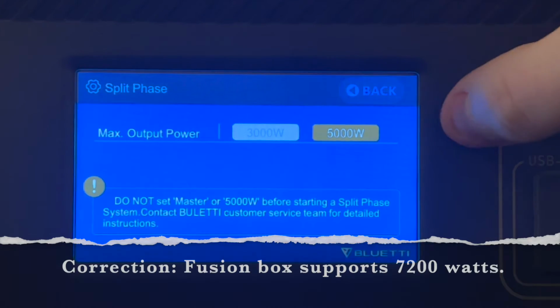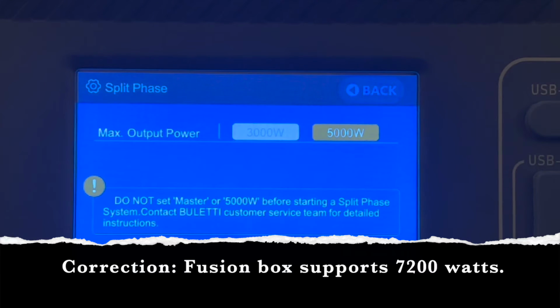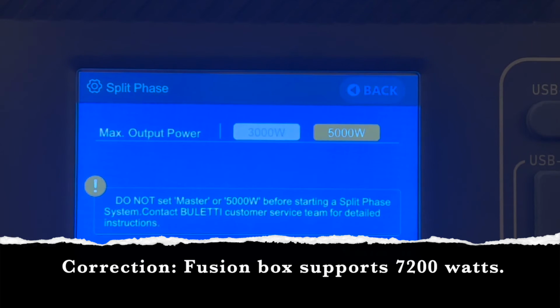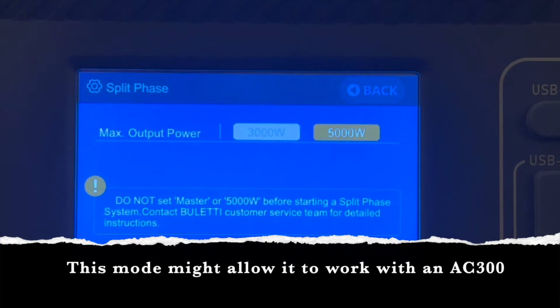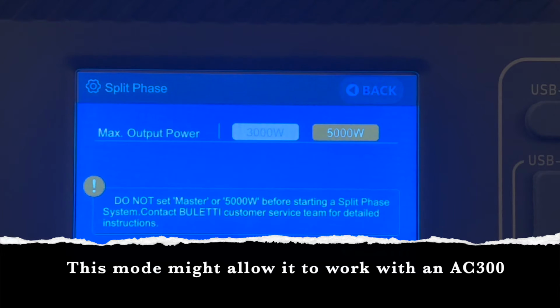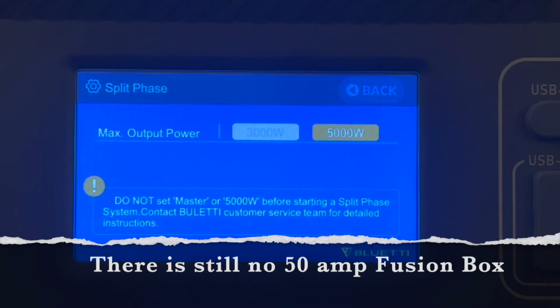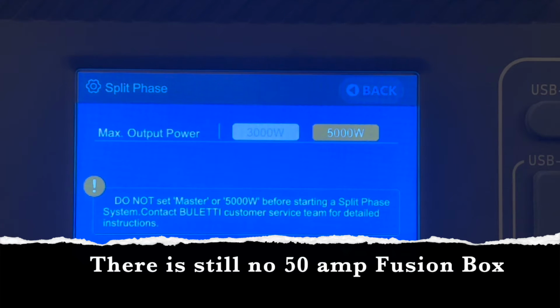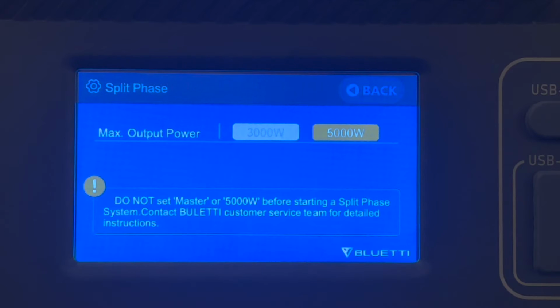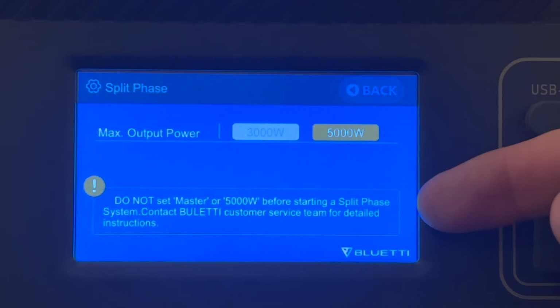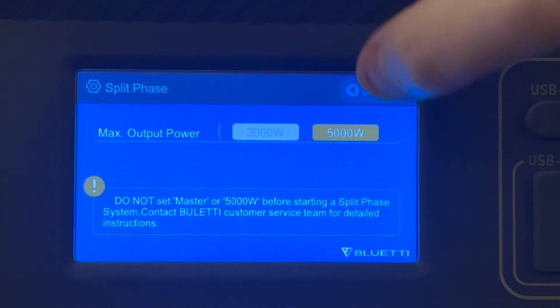Okay? And there's one more setting, the max output power. You can force the inverter to run in a mode where it will not output more than 3,000 watts. The reason for this is when the device is first being released, and they may fix this later, they do not have a separate 50 amp split phase device that's coming out with it. So the current split phase device is limited to 3,000 watts per leg, so you actually have to turn the inverter down to 3,000 watts output maximum before you can run the device in split phase mode. And it's got a warning to that effect down here at the bottom of the screen. And that's all that's in that menu.